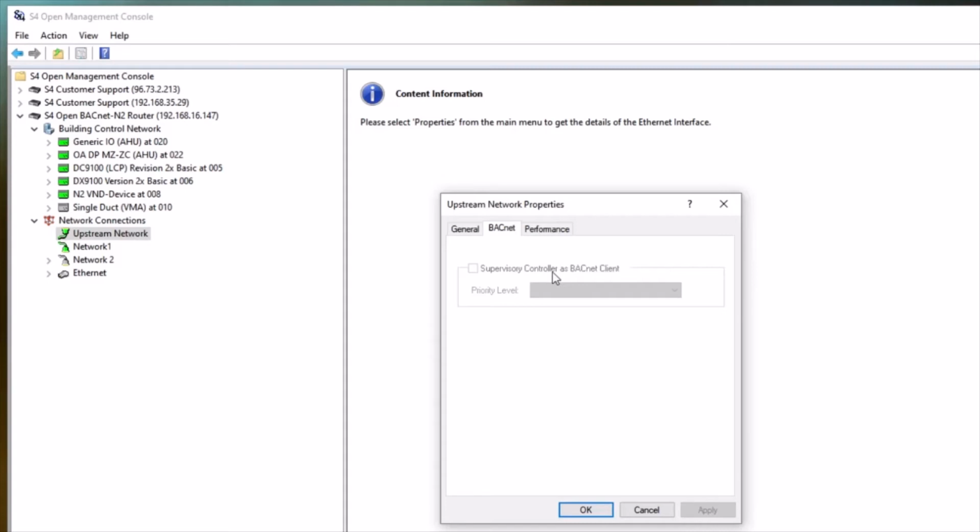You turn on the option and select the priority for the N2 transactions with the drop-down menu. N2 transactions then follow the rules of the BACnet priority array mechanism. Thus, you have a way of migrating away from Metasys control of field devices on a point-by-point basis simply by having your BACnet client operate at a higher priority level. The N2 transactions will be parked, and the BACnet transactions will be applied to the N2 field device.